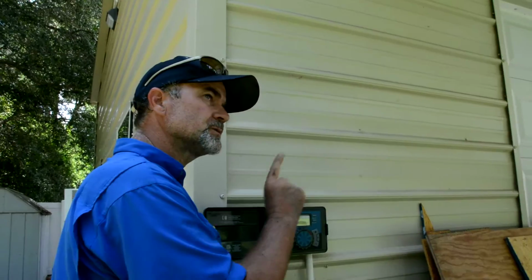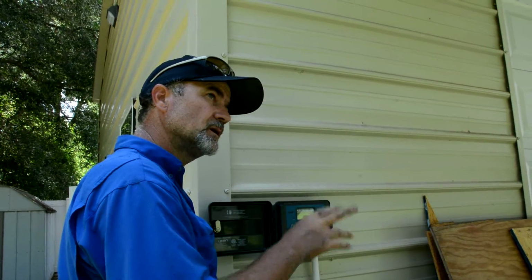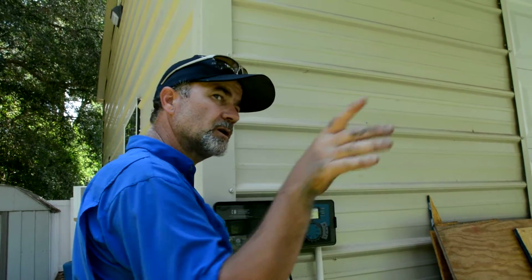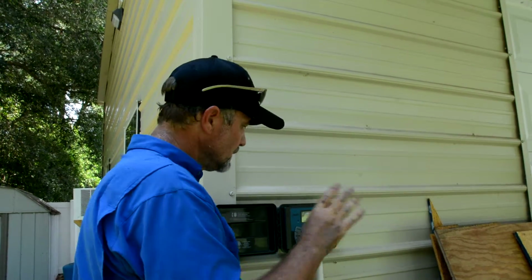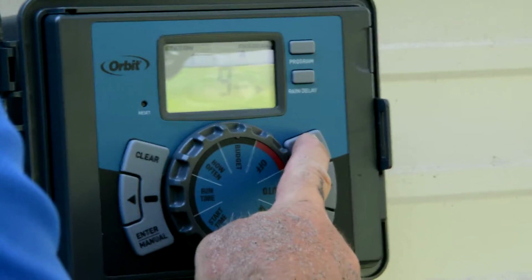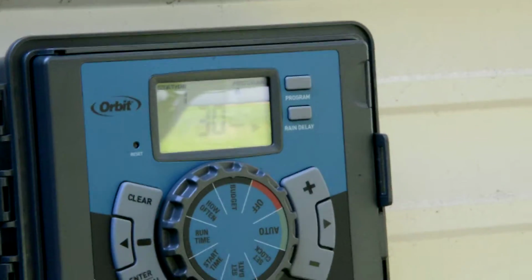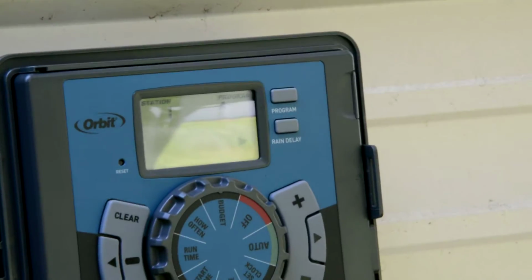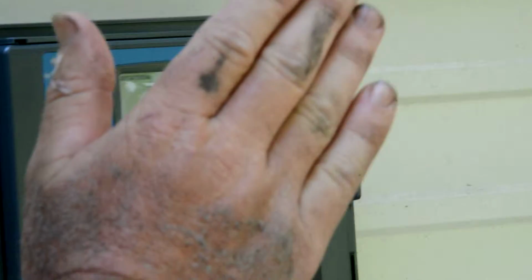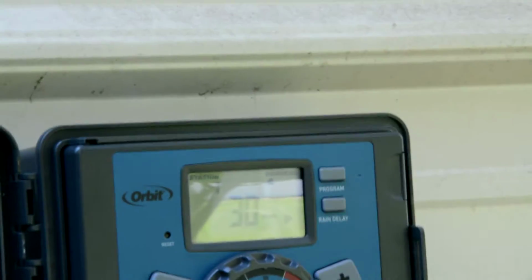You're going to have 6 independent stations. 2 for the spray areas, the little small spray sprinklers. 1 for the drip, that'll be the shrubbery around the house. And then 3 of the large rotor stations that are like going now. So 6 stations. Each station is independently programmed. You go up or down for your timing. For simplicity, let's go 30 minutes for the sprays and then 60 minutes for the rotaries for now, and then we can adjust that later.